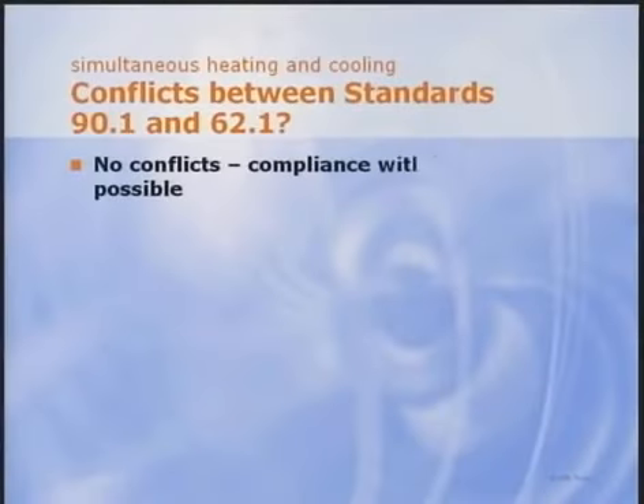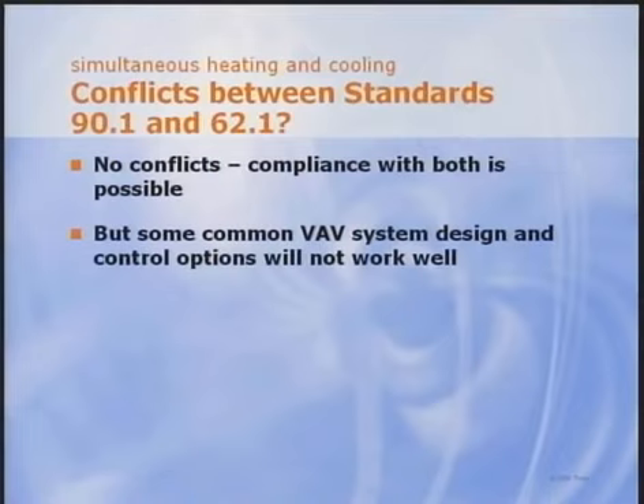Steve? Well, once again, we ask, are there conflicts between the requirements of 62.1 and 90.1 with respect to simultaneous heating and cooling? And once again, strictly speaking, there are no conflicts. It is possible to design a mechanical system that meets both standards. However, it is more difficult than the previous two potential conflicts we have discussed. Some common VAV systems will not be able to meet both 62.1 ventilation requirements and 90.1 zone reheat limitations without very high outdoor air rates.